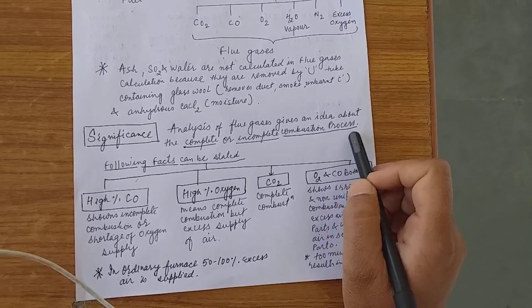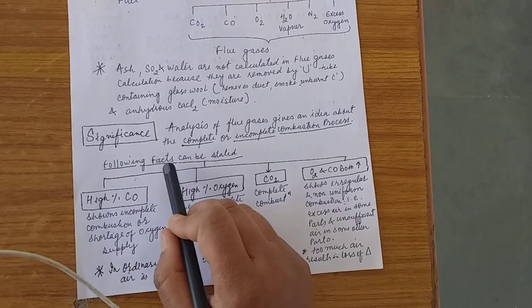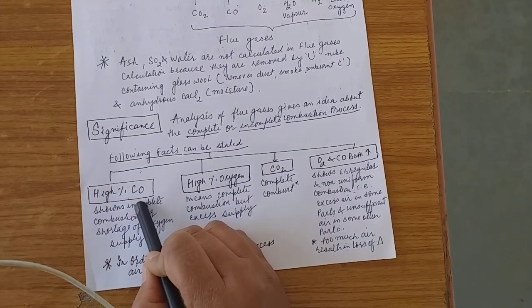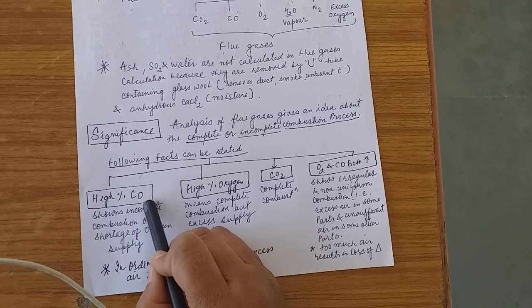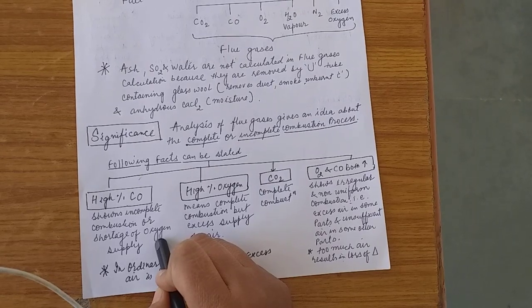This process shows complete or incomplete combustion of fuel which we are using, it may be solid, liquid, or gaseous. Following effects can be stated after combustion: if there is a high percentage of carbon monoxide, it shows incomplete combustion and also shortage of the oxygen supply.